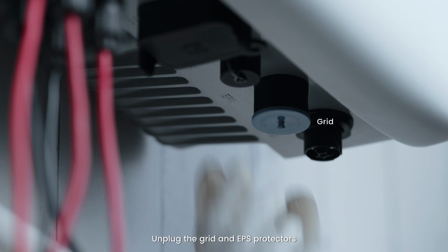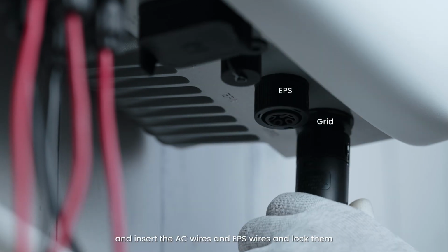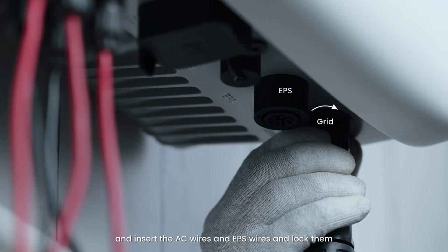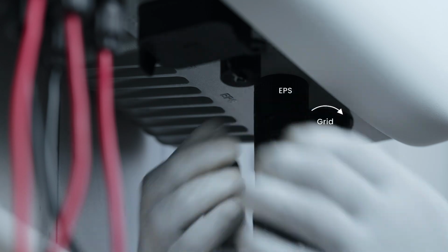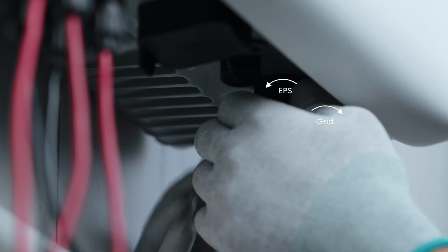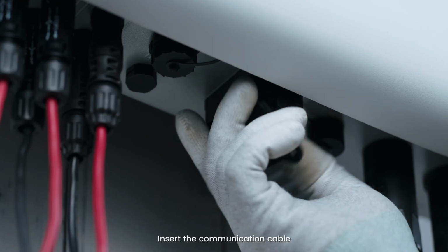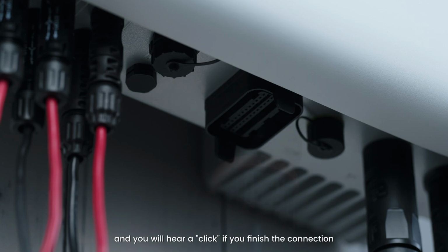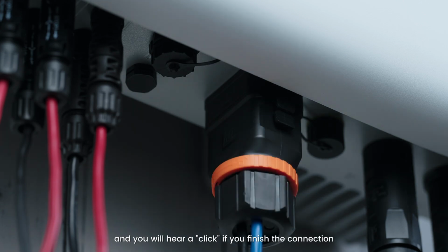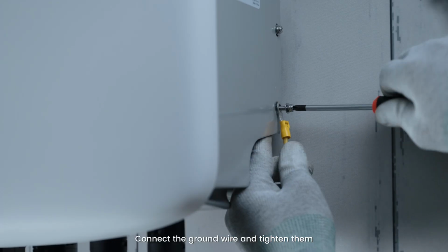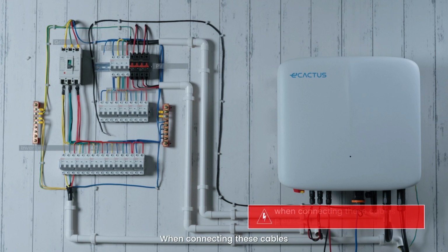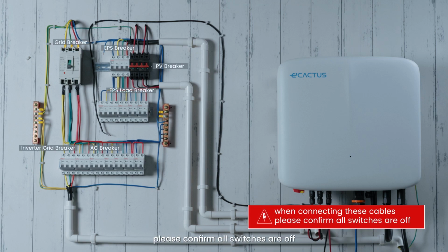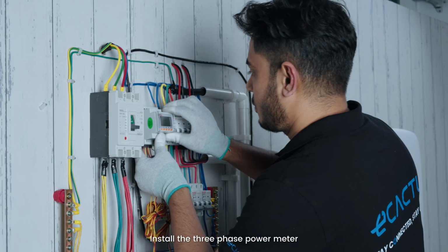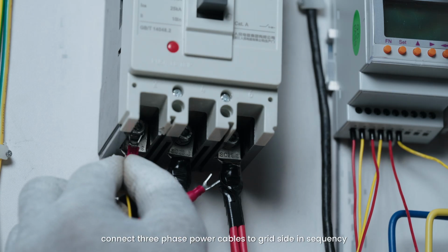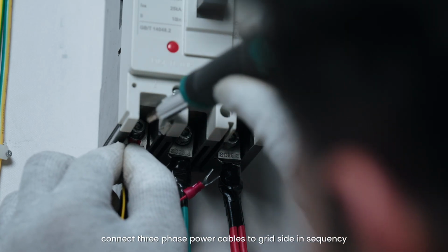Unplug the grid and EPS protectors and insert the AC wires and EPS wires and lock them. Insert the communication cable and you will hear a click if you finish the connection. Connect the ground wire and tighten them. When connecting these cables, please confirm all switches are off. Install the 3-phase power meter. Connect the 3-phase power cables to grid side in sequence.